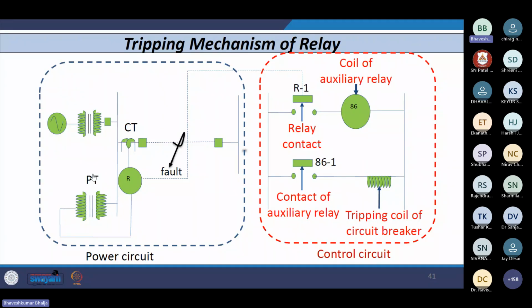So according to Slepian's theory, whenever a fault occurs and whenever the circuit breaker coil receives the signal, there is a race between the rate of rise of restriking voltage and the rate at which the dielectric strength of the insulating medium used inside the circuit breaker builds up. Let's say we use SF6 gas, which is electronegative in nature. You have studied all the features, characteristics, right? So normally, let's say 70% of the circuit breakers are SF6 in our country.